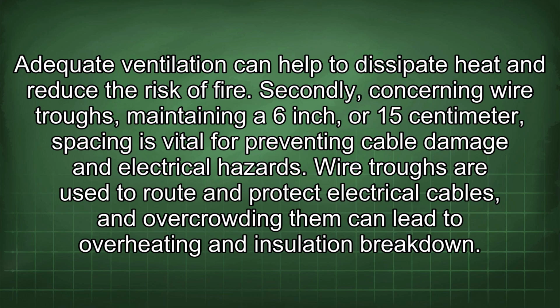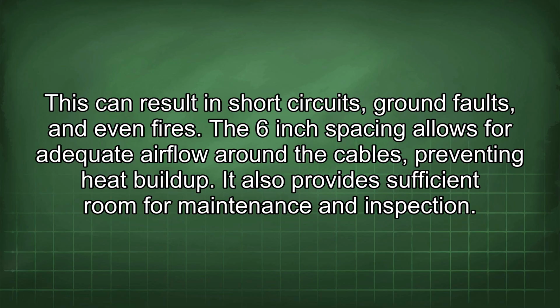Secondly, concerning wire troughs, maintaining a 6-inch or 15 centimeter spacing is vital for preventing cable damage and electrical hazards. Wire troughs are used to route and protect electrical cables, and overcrowding them can lead to overheating and insulation breakdown. This can result in short circuits, ground faults, and even fires. The 6-inch spacing allows for adequate airflow around the cables, preventing heat buildup. It also provides sufficient room for maintenance and inspection.